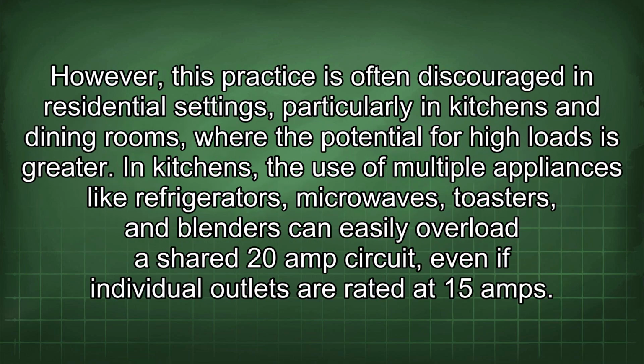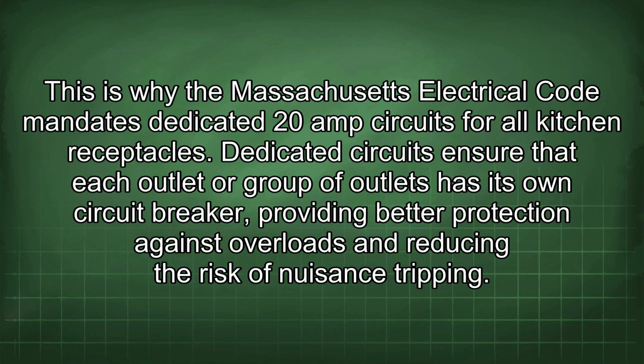However, this practice is often discouraged in residential settings, particularly in kitchens and dining rooms, where the potential for higher loads is greater. In kitchens, the use of multiple appliances like refrigerators, microwaves, toasters, and blenders can easily overload a shared 20 amp circuit, even if individual outlets are rated at 15 amps. This is why the Massachusetts Electrical Code mandates dedicated 20 amp circuits for all kitchen receptacles. Dedicated circuits ensure that each outlet or group of outlets has its own circuit breaker, providing better protection against overloads and reducing the risk of nuisance tripping.